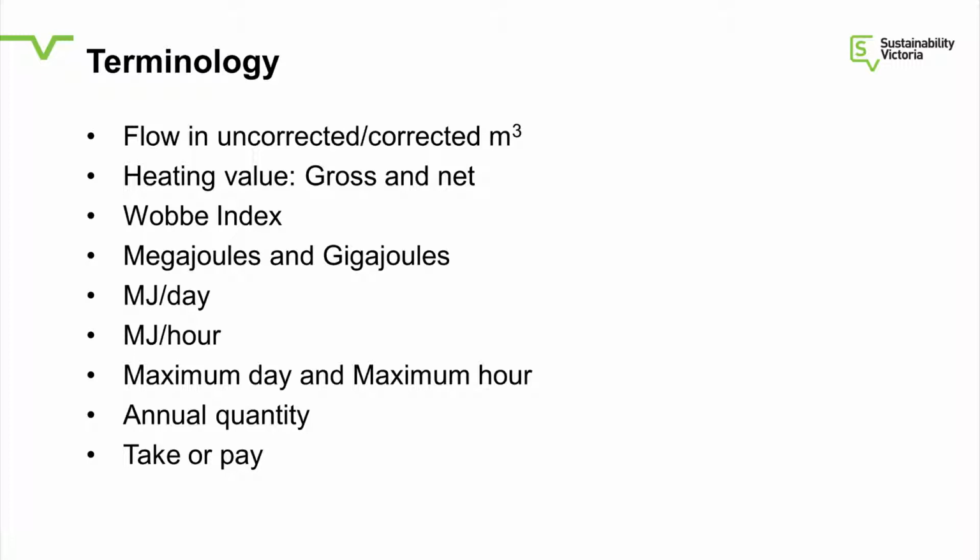The gas companies measure the heating value every half hour at all the various zones and take an average of that over the month. So you're applying an average heating value over the month to come up with the figure that they apply on your bill. It doesn't vary a lot. Typically the gas in Victoria might range from 38.4 to 38.9 megajoules of gas per cubic metre volume.